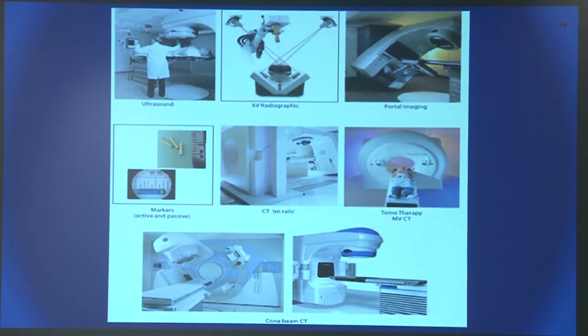Tomotherapy, as I told you, has an inbuilt CT scanner—this is a typical linear accelerator with a built-in CT scanner. This CT scan is not as perfect as a diagnostic CT scan, because what we need is only the position of the tumor. We don't need to know its characteristics, whether it's highly radio-opaque or high or low contrast—only the location. So we can use a low-resolution CT scanner, and this does not replace a high-resolution CT scanner.